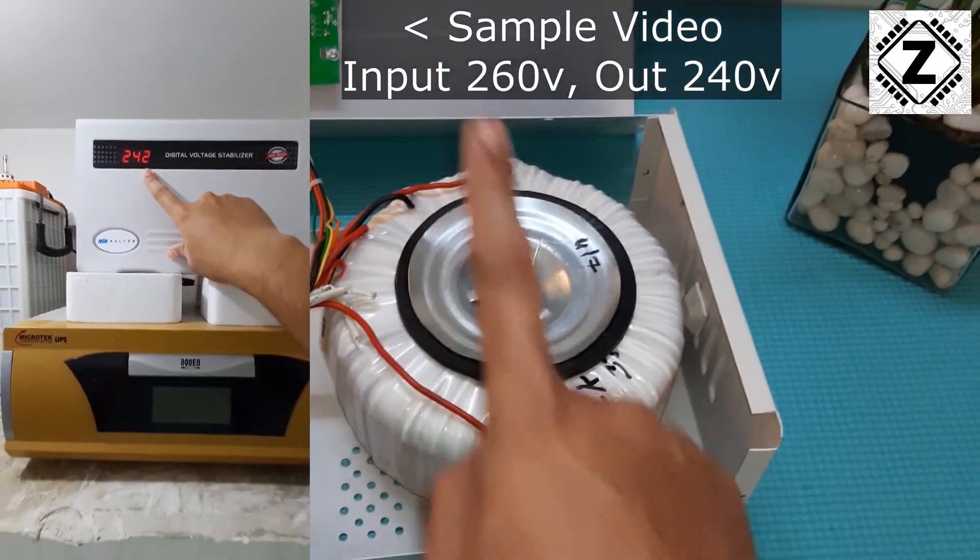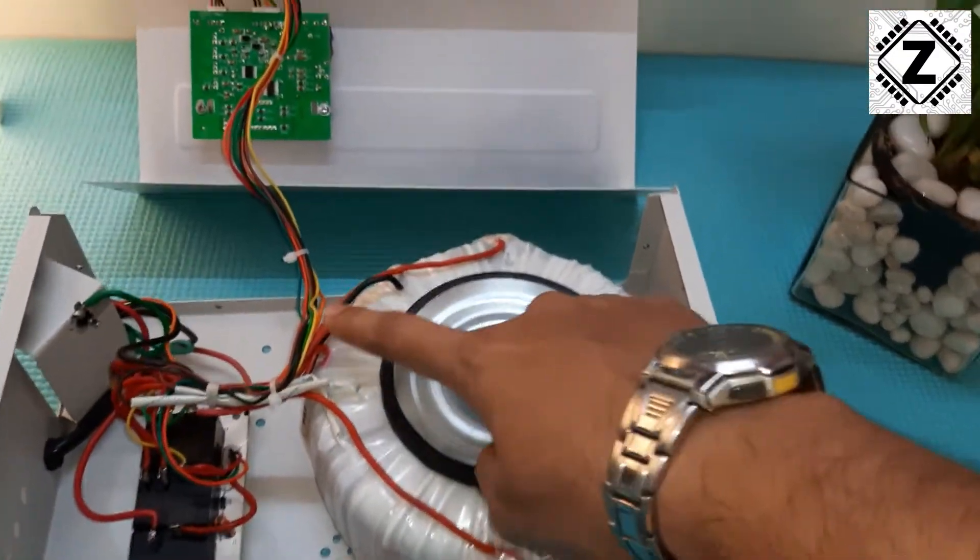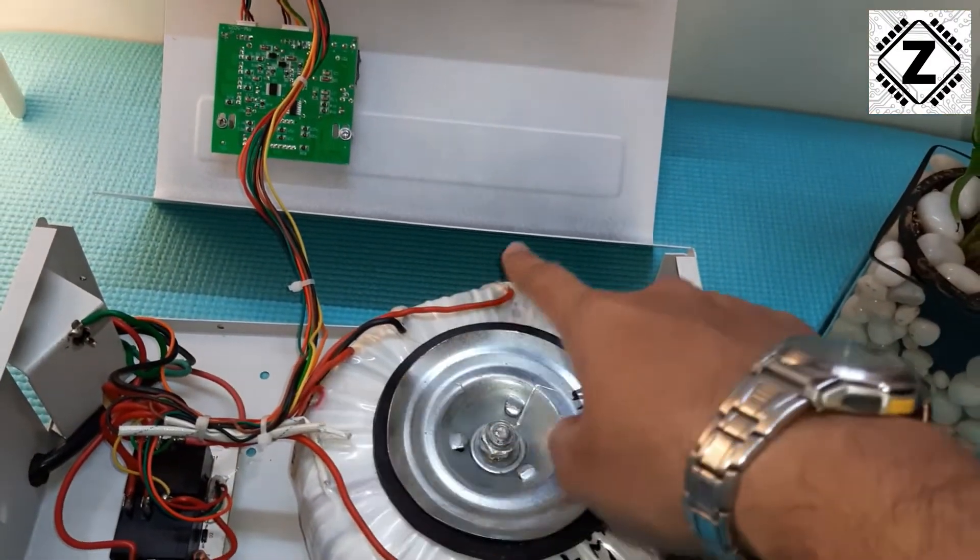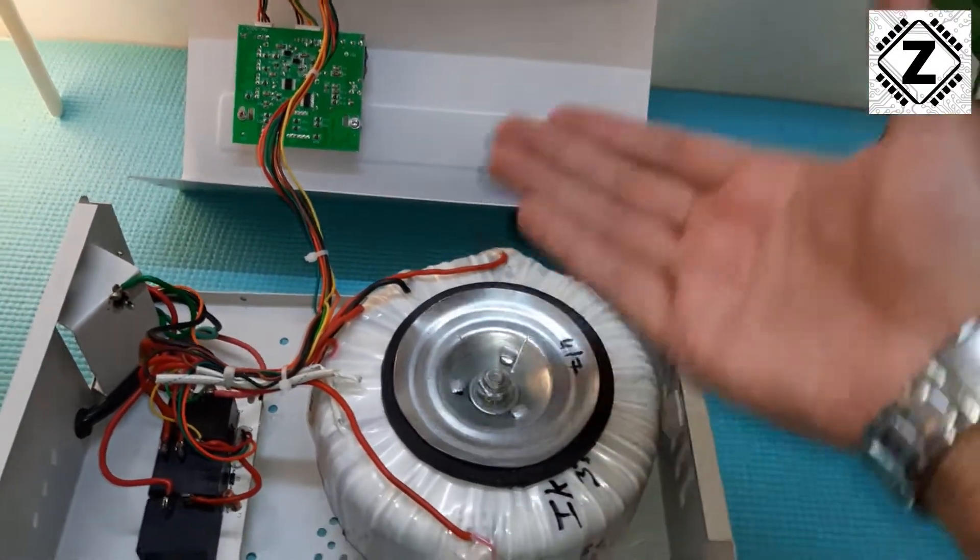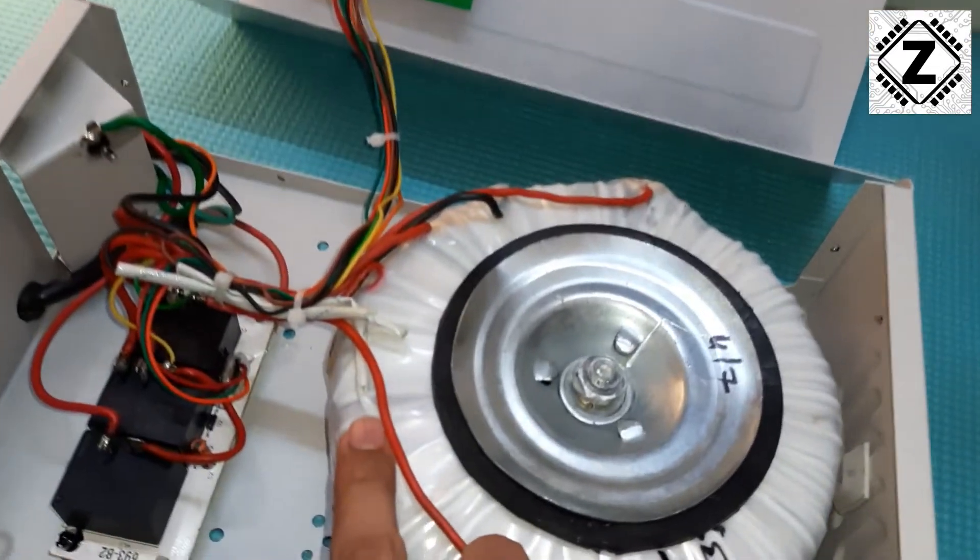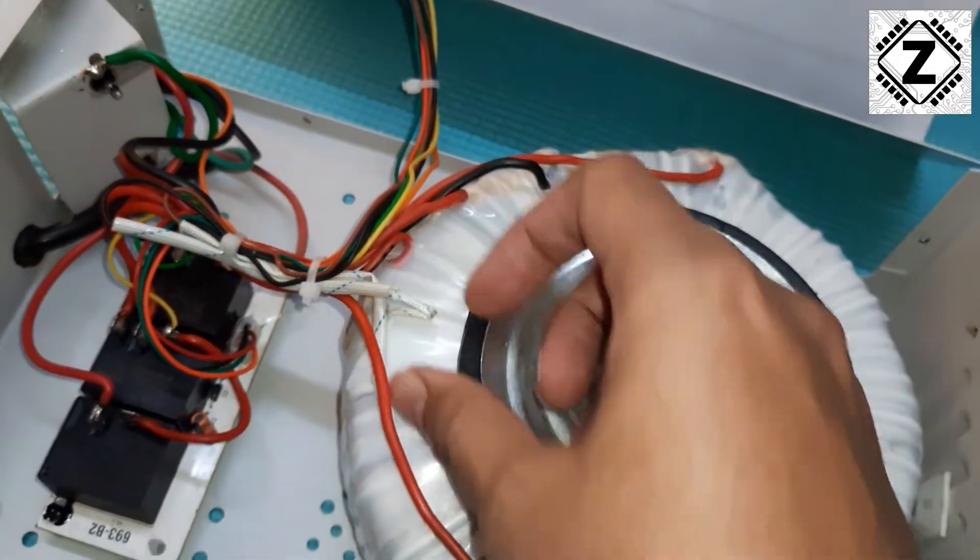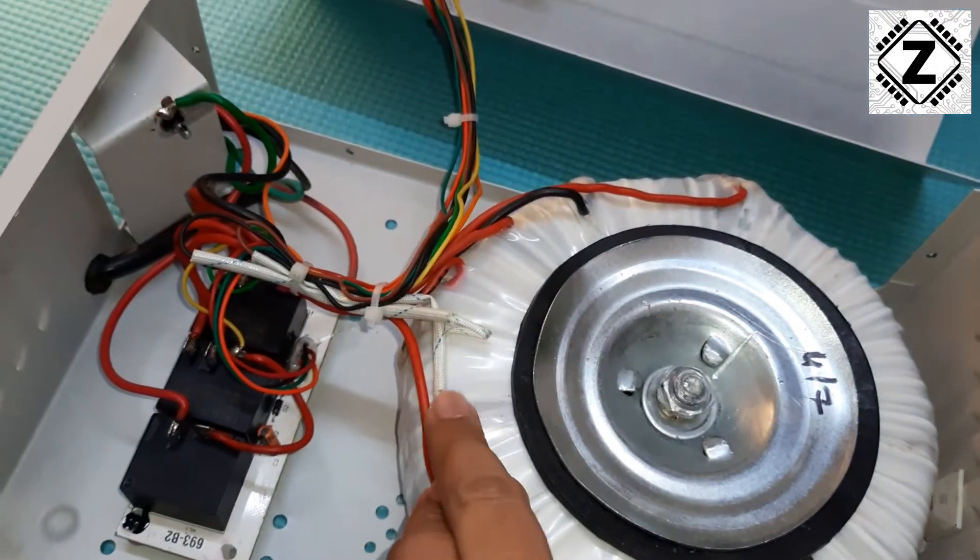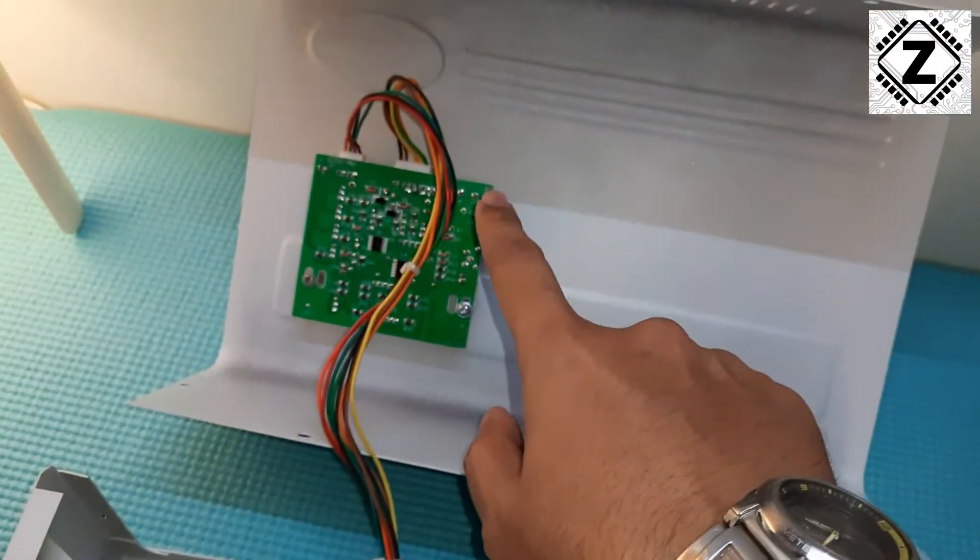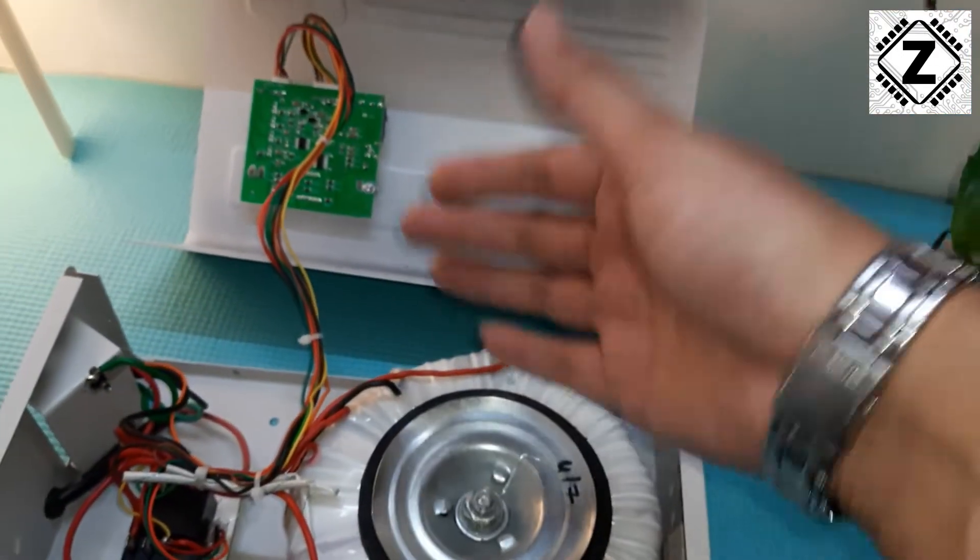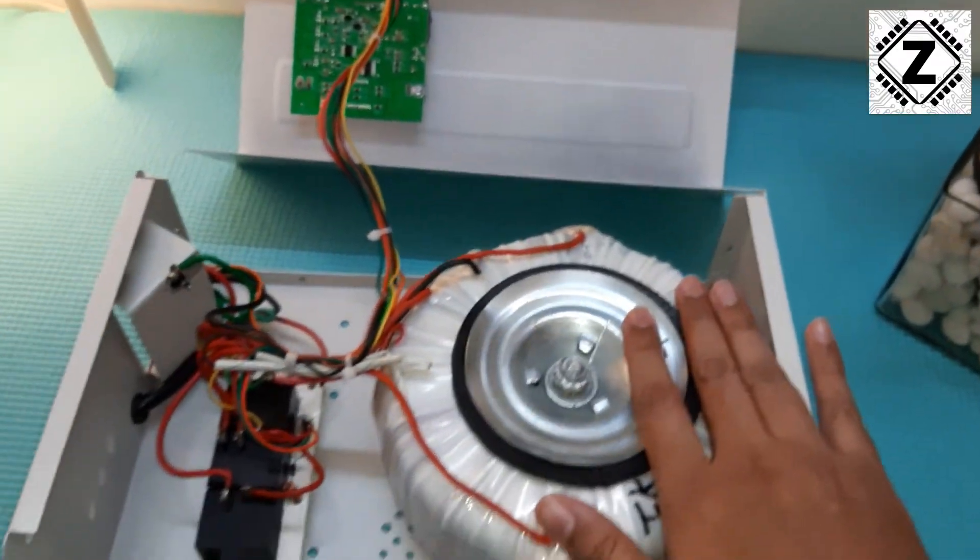tap is going to step it down. So it has one step-down tap and it has three booster taps, that is, the step-up taps. Plus there's this mysterious winding over here. Any guesses what is this? So guys, this thing actually provides power to the circuit.